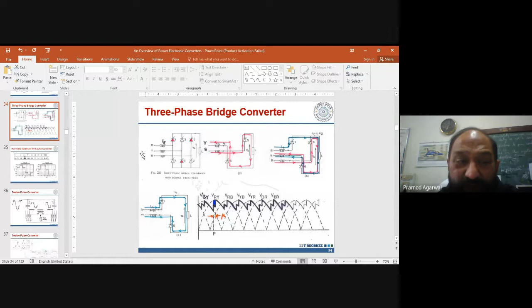So plus minus. In the very first look, it appears that the harmonic spectrum of this will be different than the harmonic spectrum of this. No. Whatever harmonics are present on secondary side, this side, same harmonics will be present on the primary side. Transformer doesn't change the harmonic spectrum. But why is the shape different? Shape is different because some of the harmonics, their sign gets changed. Like 5th and 7th, their sign gets changed. Similarly, 17th and 19th, their signs get changed. And if you add those current harmonics, you will get this type of current waveform rather than this one. So in the first look, it appears that the current harmonics are different in the two, but they are not. They are the same.